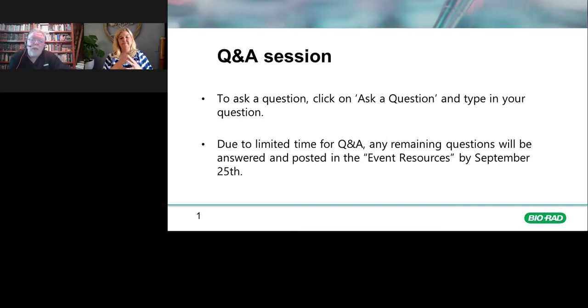So the first thing I would say is that the fact that you have a 1.3S error is not what you need to be looking at. What you need to be looking at is, what is your designed QC strategy? So if your designed QC strategy is that a 3.5 standard deviation error is when you would reject, then you wouldn't pay any attention to a 1.3S error. So the actual QC rule that is designed is what you should be paying attention to.